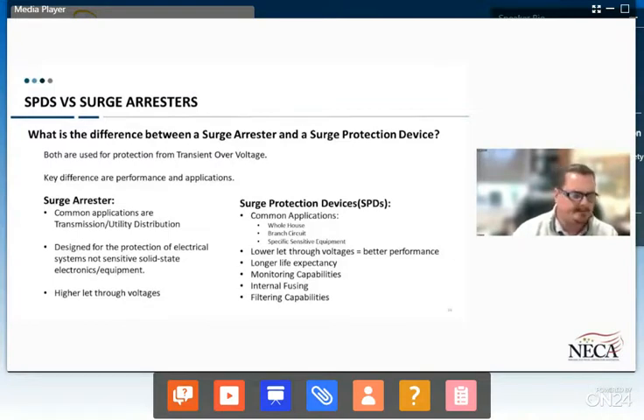They're not really intended to protect some of those solid state electronic type equipment that were talked about in the previous slides. Surge protection devices, or SPDs, really are those devices that are more designed. They have lower let-through voltages. Some of the common applications for those are whole house protection, branch circuit protection, or even specific equipment protection. They have monitoring capabilities, a little more smarter of a device, internal fusing and filtering capabilities, and then a longer lifespan. Certain manufacturers will say that their devices will last 25 years, maintenance free. So again, those are some of the key differences.